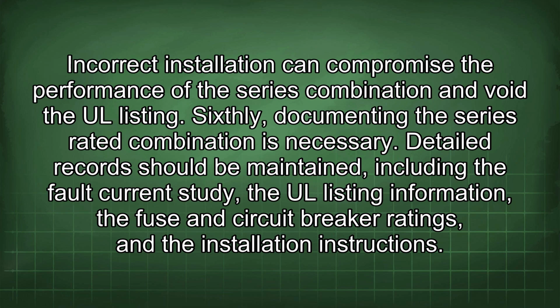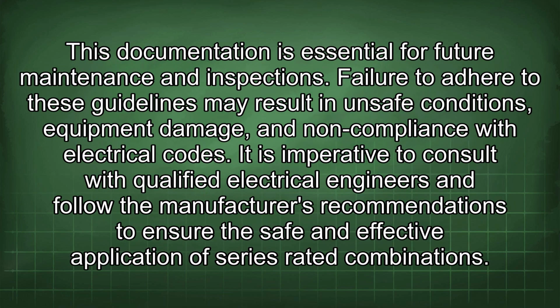Sixthly, documenting the series-rated combination is necessary. Detailed records should be maintained, including the fault current study, the UL listing information, the fuse and circuit breaker ratings, and the installation instructions. This documentation is essential for future maintenance and inspections. Failure to adhere to these guidelines may result in unsafe conditions, equipment damage, and non-compliance with electrical codes.